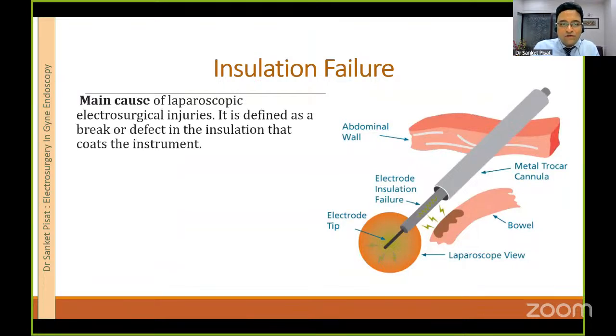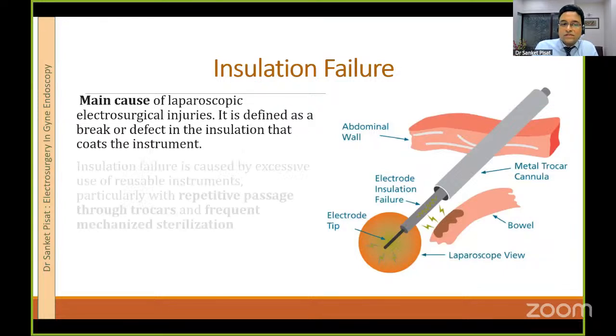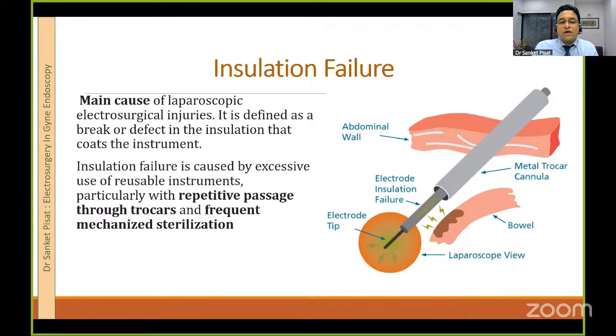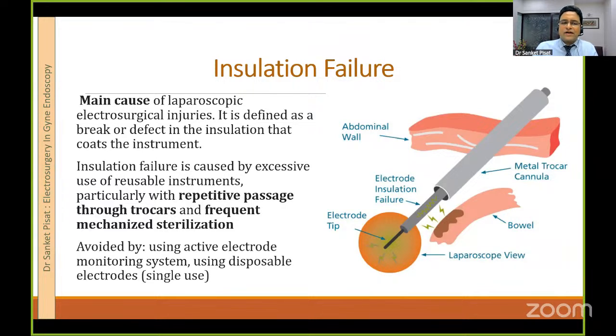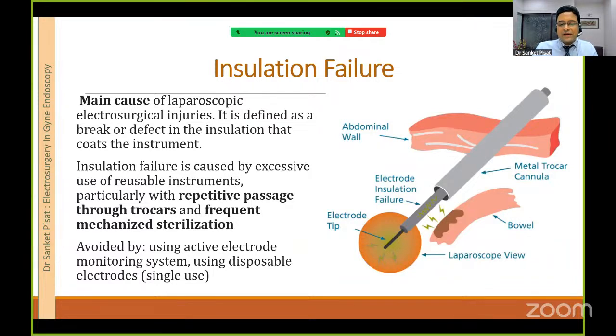This is the main cause of laparoscopic electrical injuries and is defined as a break in the insulation that coats the instrument. Insulation failure is typically caused by excessive use of reusable instruments. You know, the black coating that we have over the instrument gets worn out over time, and repetitive passage through trocars and frequent sterilization like autoclaving will damage the external insulation. This can be avoided by using what we call an active electrode monitoring system, but that is a little bit theoretical. The best is to use disposable or single use electrodes. And if you are using reusable electrodes, then discard them after a few uses.